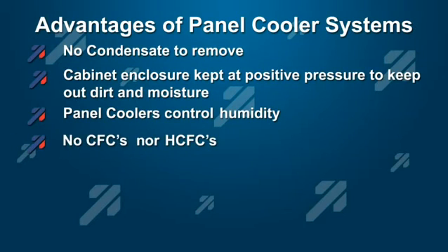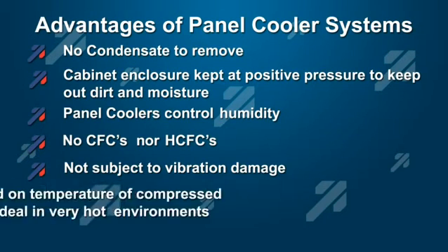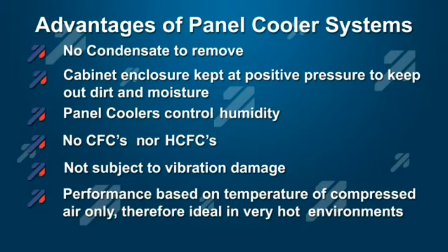No CFC's or HCFC's are involved. Panel coolers are not subject to vibration damage. Performance is based on the temperature of the compressed air and not the temperature of the environment, so they are actually much more efficient and reliable in extremely hot situations. Essentially, they are maintenance free.